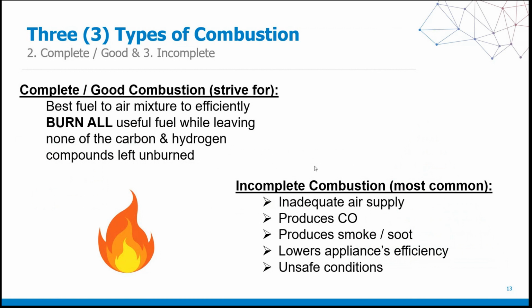However, for those of us that are not using a combustion analyzer, we seem to hover in the incomplete combustion category. And that is the third type of combustion, incomplete. And that is where, due to inadequate air supply, we're producing carbon monoxide in higher ppm or concentrations than what is allowable. We're producing smoke and soot and other unsafe byproducts of combustion, such as NOx and the like. And we're also lowering the efficiency of that appliance.